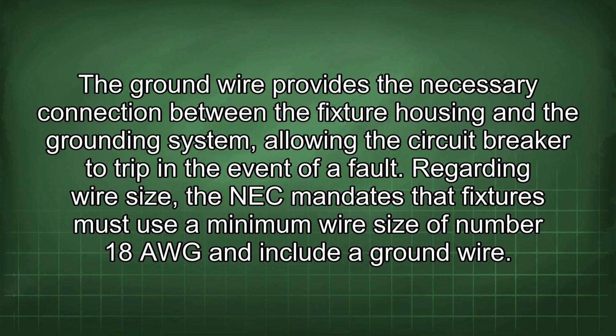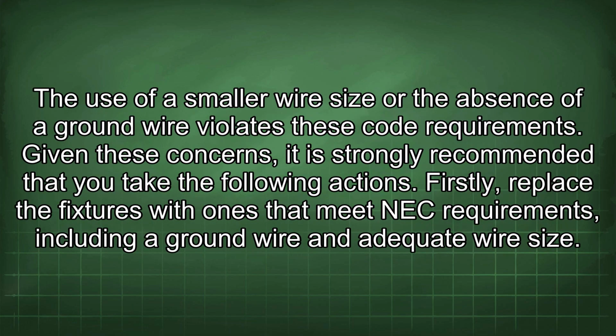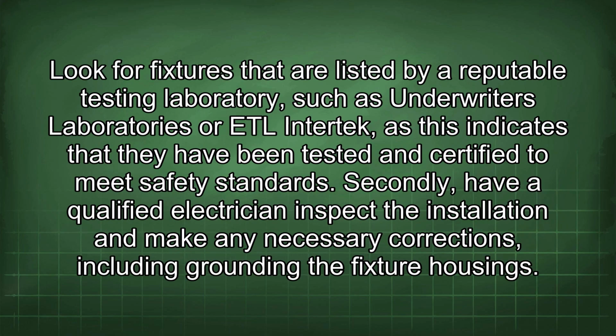Regarding wire size, the NEC mandates that fixtures must use a minimum wire size of number 18 AWG and include a ground wire. The use of a smaller wire size or the absence of a ground wire violates these code requirements. Given these concerns, it is strongly recommended that you take the following actions. Firstly, replace the fixtures with ones that meet NEC requirements, including a ground wire and adequate wire size. Look for fixtures that are listed by a reputable testing laboratory such as Underwriters Laboratories or ETL Intertek, as this indicates that they have been tested and certified to meet safety standards.